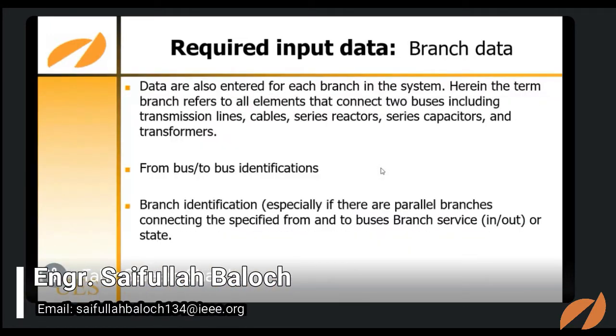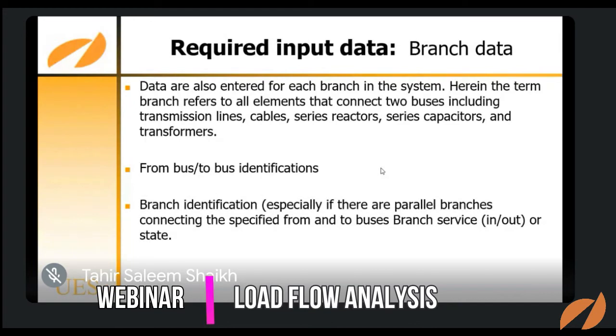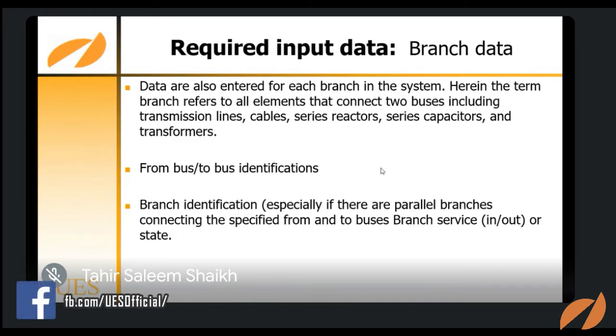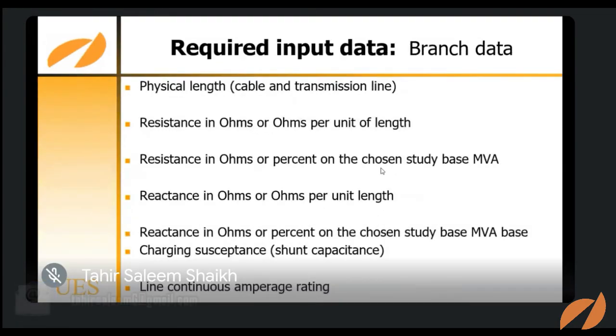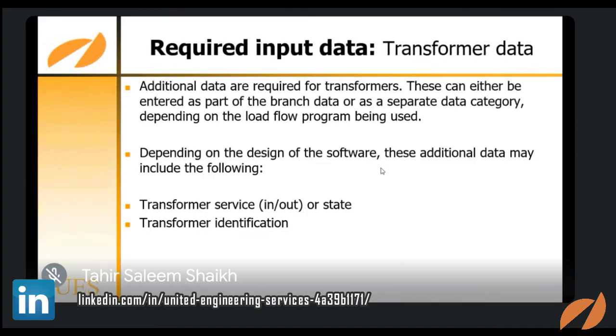Now branch data. Branches can be parallel or series, depending upon the system needs. There can be transmission lines, cables, series reactors, series capacitors and transformers. Okay, so for the branch data you need to insert the physical length and the resistance in ohms. You can also have per unit parameters for the reactance and the line continuous amperage rating. So these are the data you need to put.